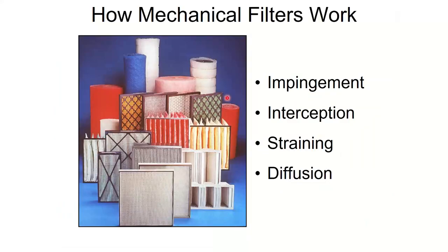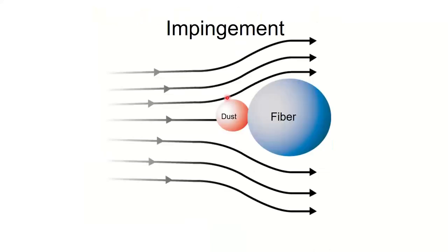So mechanical filters, how do they actually work? They use 4 different mechanisms to catch stuff. First one's impingement. This one's super easy for me to describe. This blue circle here, this fiber, could be a piece of fiberglass. It could be plastic, some type of polymer. It's something that's built into my filter, interwoven in there. And then for this purpose, my particulate coming into the air system is dust. So he's moving along the airstream over here. He has a head-on collision with the fiber, he sticks right on the fiber. He crashed into the brick wall.